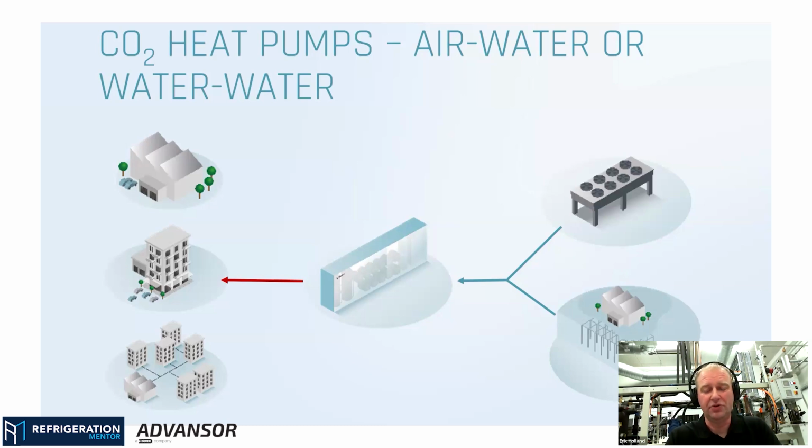So your air temperature sensor is actually mounted in the airflow of the gas cooler, and it's not placed just next to the hot exhaust from some other equipment. Your return gas temperature is mounted correctly on the return lines and insulated and protected from weather and all that stuff. So all these checks you need to do as installer on site.